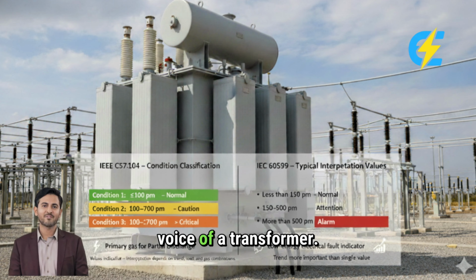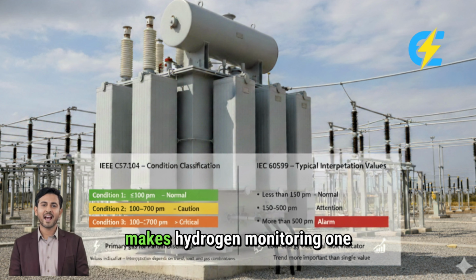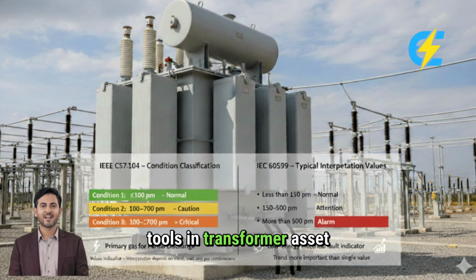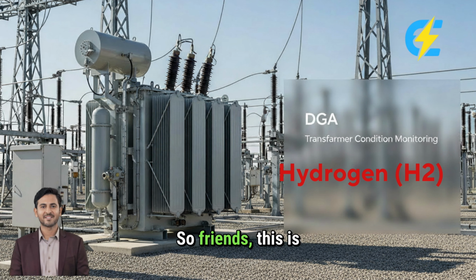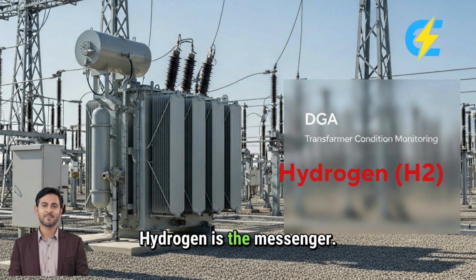Hydrogen is the earliest voice of a transformer. It whispers before the transformer screams. If you listen early, you prevent failures, outages, and asset loss. This early warning capability makes hydrogen monitoring one of the most valuable tools in transformer asset management. When you understand hydrogen's message, you gain the power to act before problems become critical, ensuring reliable power delivery and protecting valuable transformer assets. So friends, this is the real science behind hydrogen in transformer DGA. Not just numbers, not just limits, but meaning. Remember this one golden rule. Hydrogen is not the fault. Hydrogen is the messenger. It tells you how insulation is behaving, how electrical stress is developing, and whether a hidden problem is slowly growing. If you read hydrogen correctly, you don't react in panic.